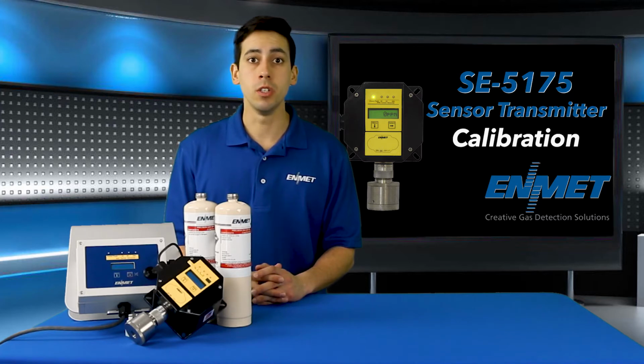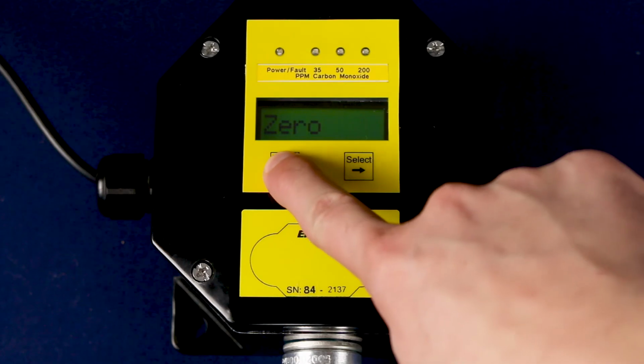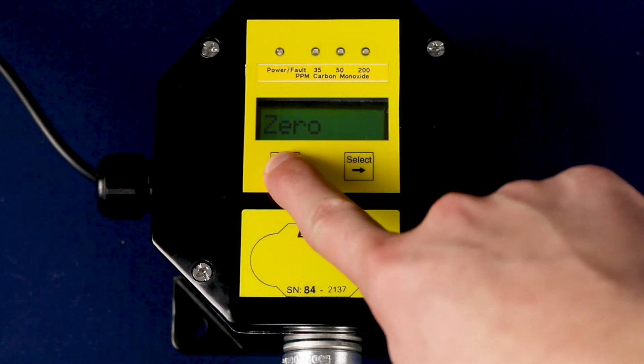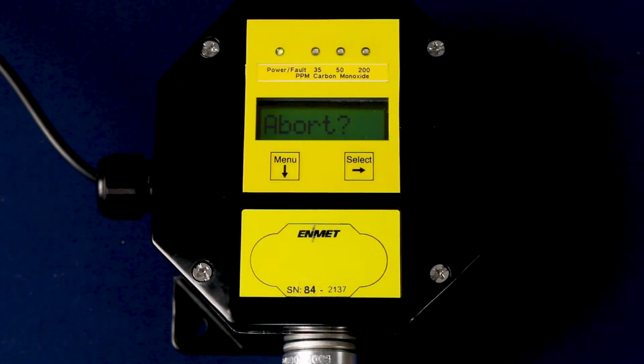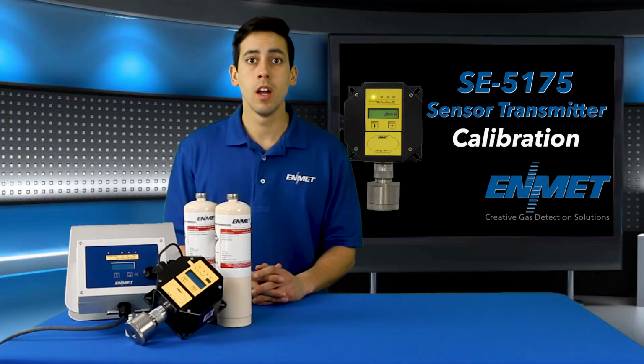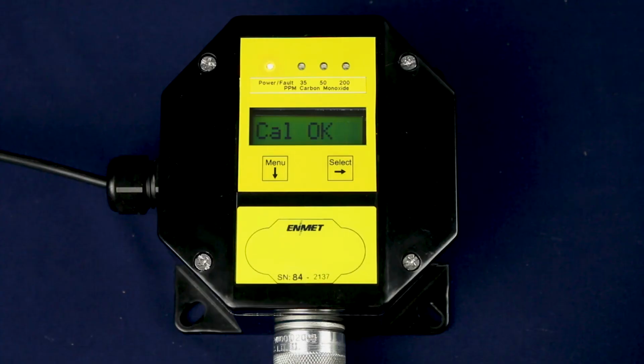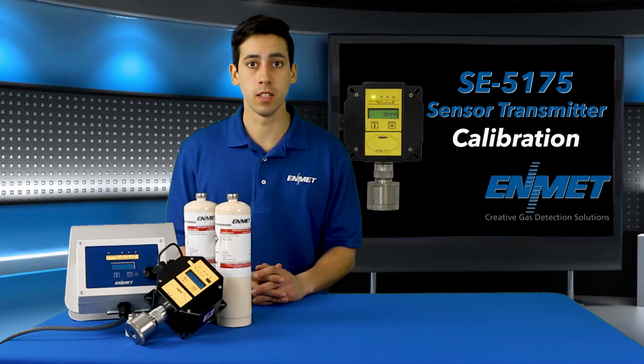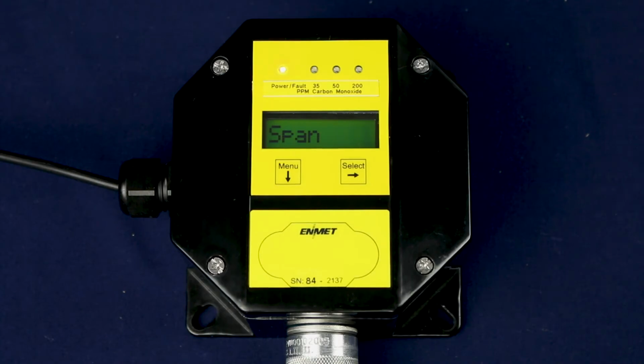If for any reason you need to abort the zero calibration, press and hold the menu button for 3 to 4 seconds, and Abort will appear on the display. Press Select to abort the zero calibration. If the reading stabilizes within the pre-programmed parameters, an automatic zero adjustment will be made, and Cal OK will appear on the display for 2 to 3 seconds. It will then take you back to the maintenance menu with the span option highlighted.